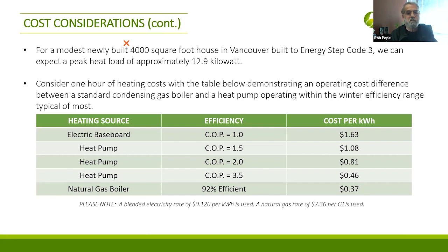When it comes to operating costs, we'll go through this quickly. This is a typical 4,000 square foot home. What you're going to see here is what it takes to heat it for one hour. If you have electric baseboard, that's the baseline—a COP of 1, meaning 1 kilowatt of electricity in gives you 1 kilowatt of heat out. It's 100% efficient, and it would cost $1.63 in this house.